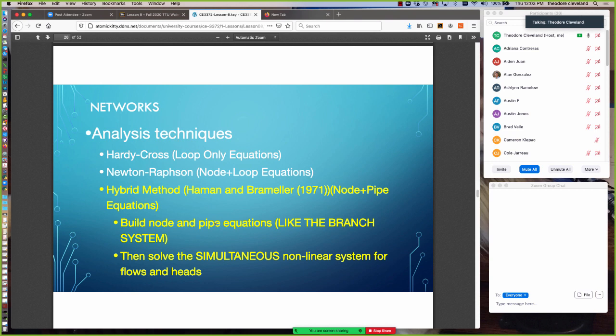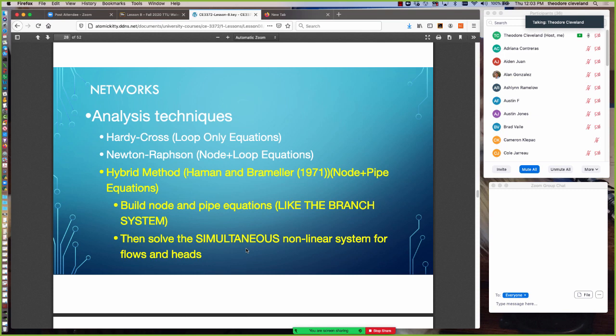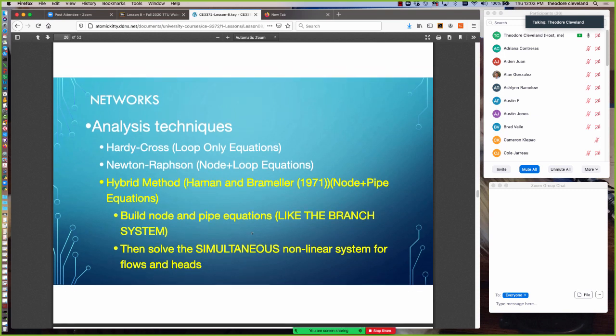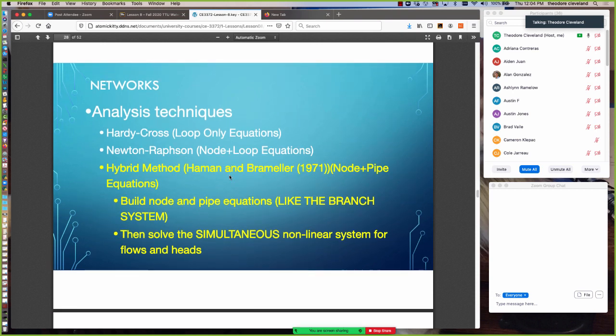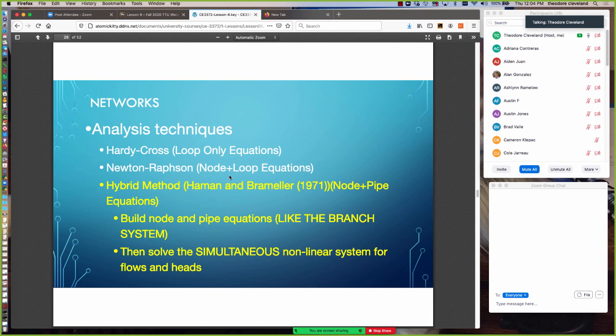it's a useful tool, and when combined with actuators, can be used for automated control. And that's pretty much how automated control pipeline systems work, is that it's running a hydraulic model in the background all the time. It's checking its sensors, and if the sensor detects a change, it can send the change to the hydraulic model right away, and the computer control algorithm can figure out what the change should produce and possibly move an actuator to achieve a desirable network state.